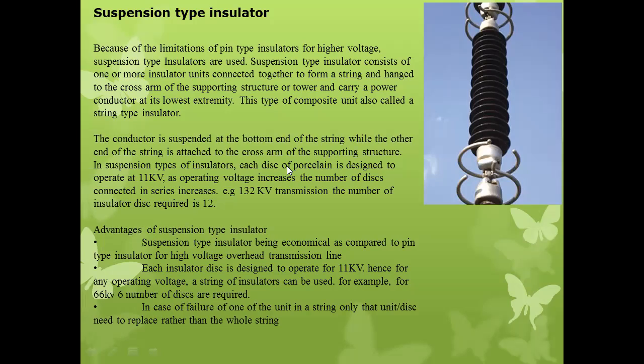It means an individual disc has the capability to withstand a voltage level of up to 11 kilovolt only. So remember this point. Each unit or disc of a suspension type of insulator is designed to operate at dash dash dash kilovolt. They will ask you this, so remember this point, 11 kilovolt. Next, an example is given here. For a 132 kilovolt transmission line, the number of insulator discs is 12. So if we transmit 132 kilovolt, you have to use a suspension type of insulator having 12 units.